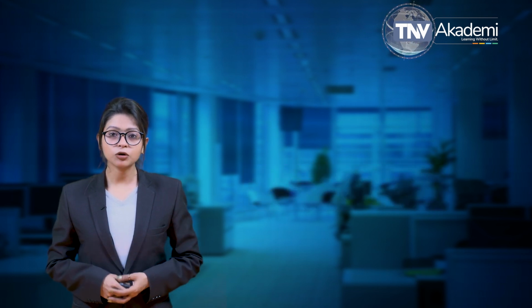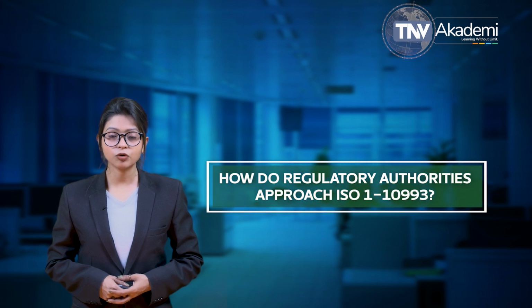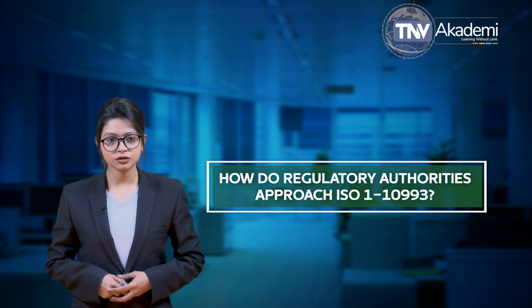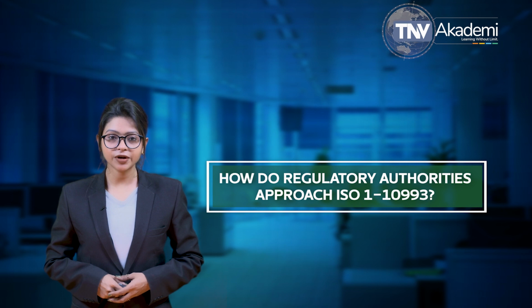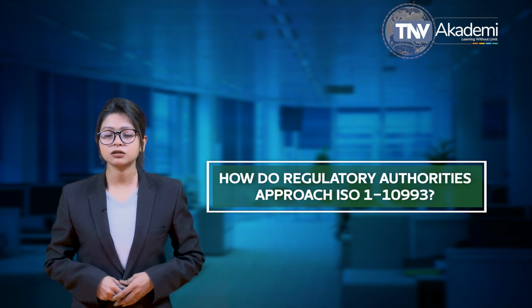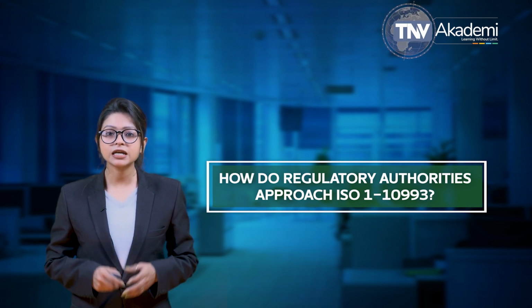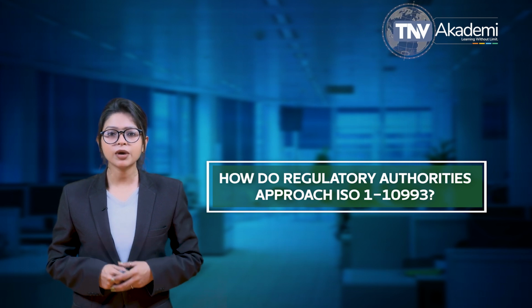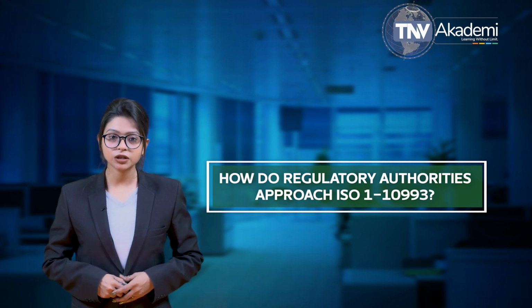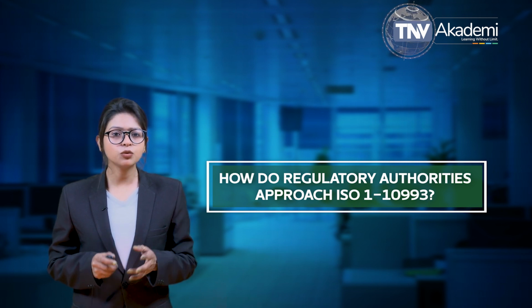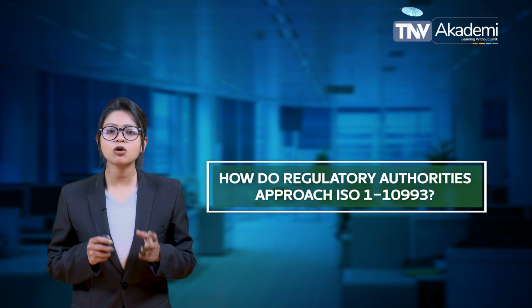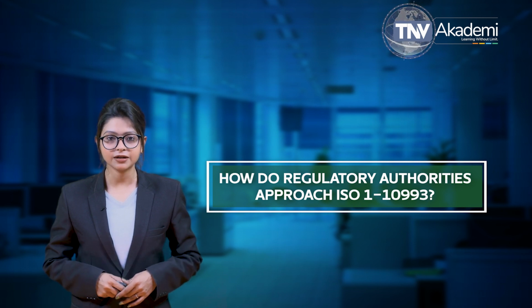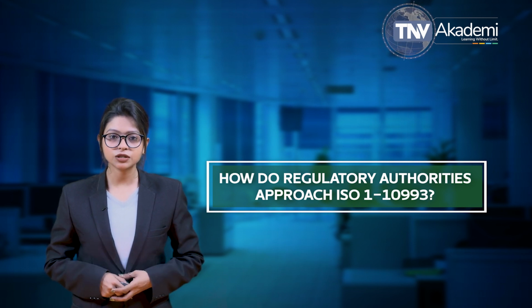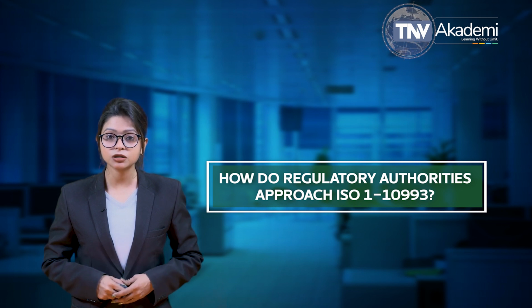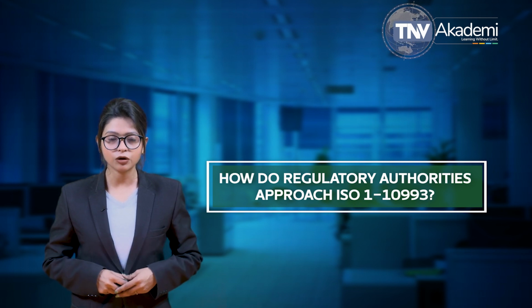Now we will talk about how regulatory authorities approach ISO 10993-1. Every region has different interpretations and preferences for what they want to see in the application process. Not to mention, while the EU for the most part accepts ISO standards with exceptions, the US FDA does not recognize all ISO 10993 standards. So simply following ISO standards may not result in the acceptance of your biocompatibility evaluation.